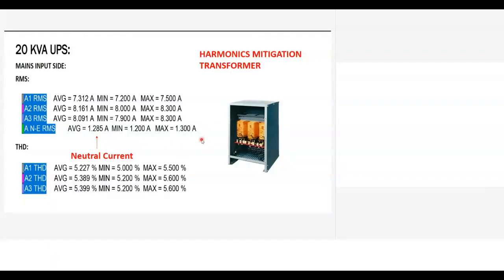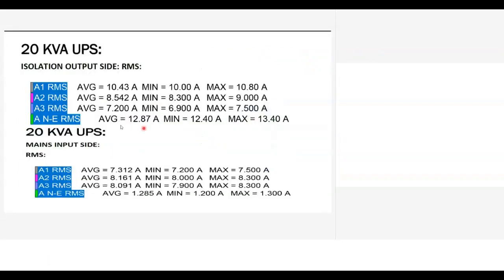So it is very ideal instead of using a K-rated isolation transformer. K-rated is nothing but you have K9, K13 and all, which means that it has to withstand 9 times the temperature rise. So you have to wind it in such a way that it withstands that. They use multiple windings and double neutral and all that in the K-rated. It becomes expensive. But even after spending that much, you don't filter the harmonics.